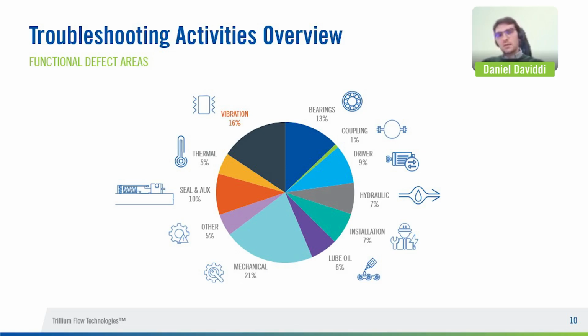In this slide, we present a pie chart summarizing the troubleshooting activities conducted in 2024 on centrifugal pumps, divided by defect area. As you can see, vibration troubleshooting issues account for a significant 16% of the total. It's important to note that this functional classification is made considering only the main cause for which the customer contacts us. But we need to consider that vibration problems may be linked to other areas as a secondary cause or contributing factor. For example, an issue with bearing installation can lead to a vibration problem. The same with the opposite scenario, because high vibration during operation can lead to premature bearing failure.